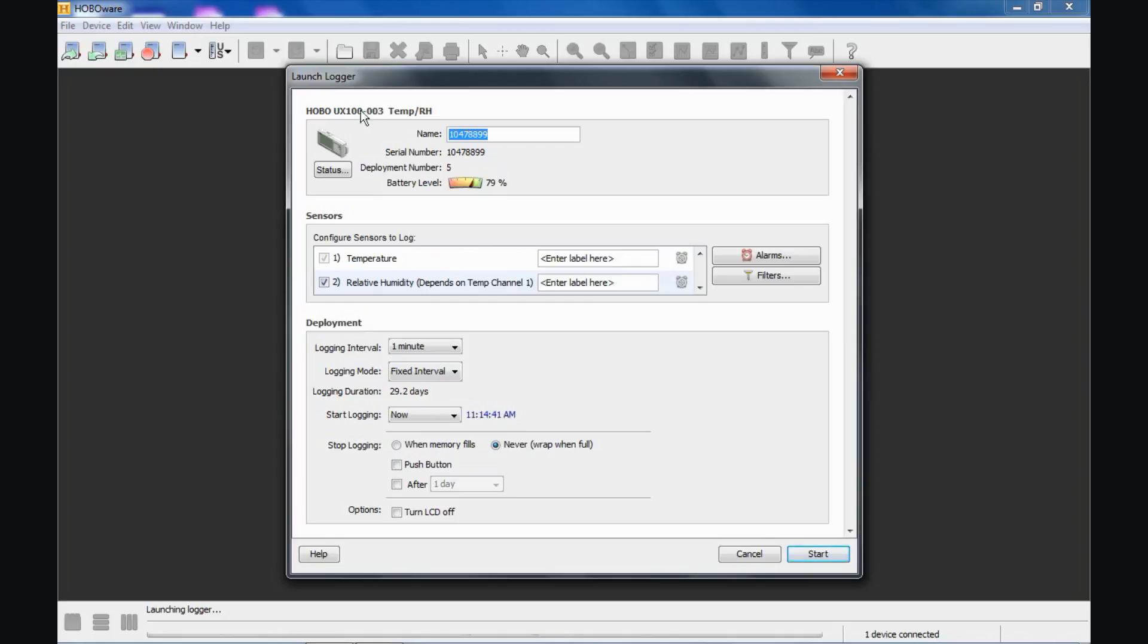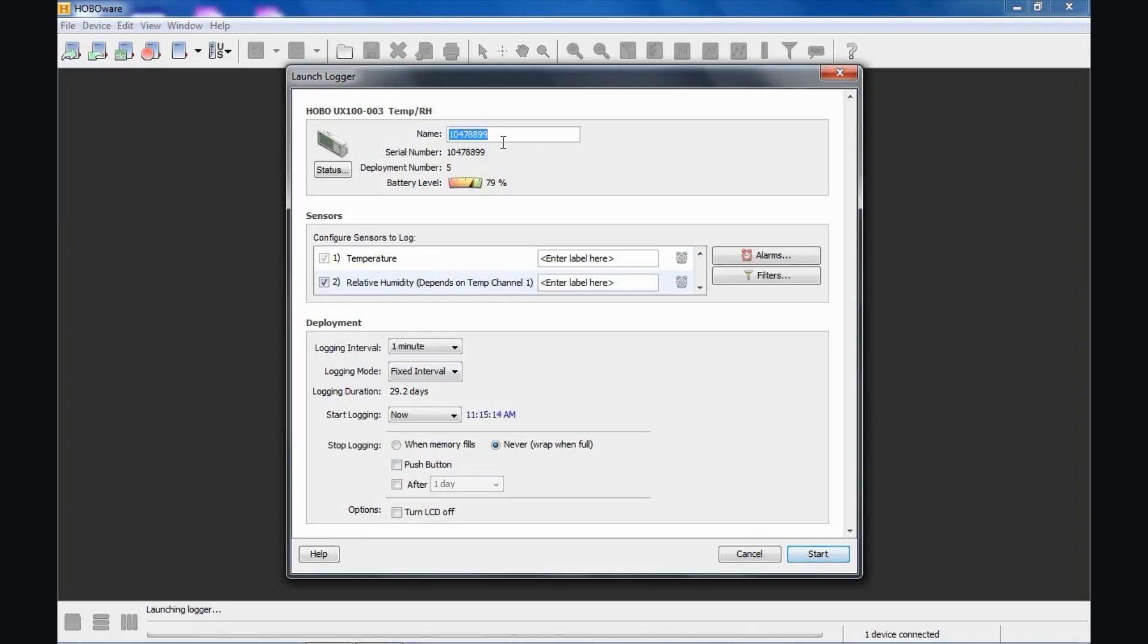Reading from top to bottom, here is our model number of our data logger. There's a place to put in a name. By default from the factory, the name of the deployment—again, you're naming this particular launch of the data logger, this deployment—by default it's the serial number. This name will be the file name of your data file when you read the data out. So in this case, it would be the serial number dot hobo would be your file name. We suggest using a name for each deployment that makes sense to you so that when you accumulate many different data files over a period of time, you can differentiate them from each other just by looking at the name. It's a lot easier than having to decipher what the serial number might mean.